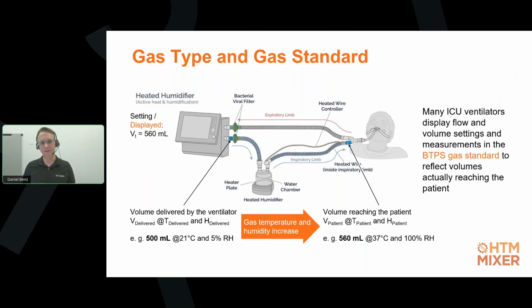37 degrees Celsius is also the typical body temperature. The gas condition at this temperature and 100% humidity is typically called the BTPS standard. That stands for body temperature and pressure saturated. Therefore, many ventilators, particularly ICU ventilators, display settings and measurements in the BTPS gas standard to reflect volumes actually reaching the patient. So what is the issue here?